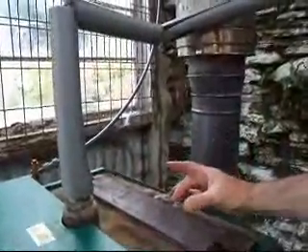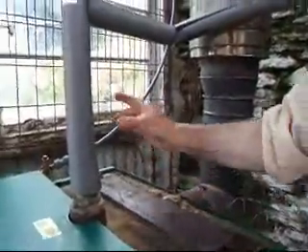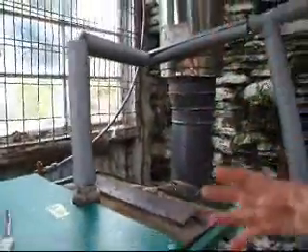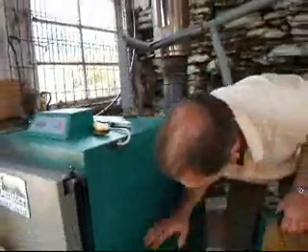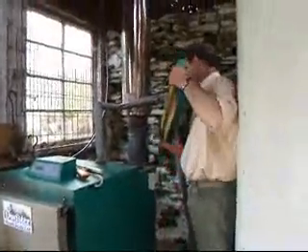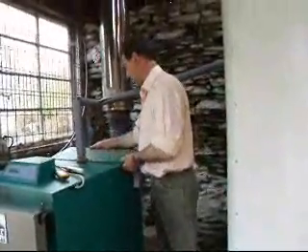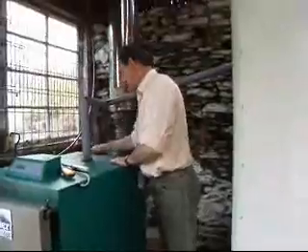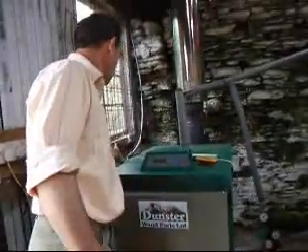There are some tubes at the back here which need to be cleaned out every month. This plate comes off — it's hot right now — and there are some tubes that go down through the back. Because it's a down-burning boiler, the flue gases go downwards along the bottom and up through the tubes in the boiler.